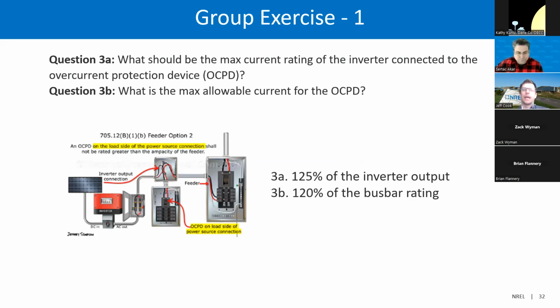And then for 3B, the maximum allowable current is 120% of the bus bar. So those are more of the common things you might see as issues, and you would typically see where they might have approved something on the plan, but you're seeing something installed larger or smaller out in the field than what's on the plan. And so that'd be something, of course, you'd reject. This is something that should be caught at plan review, and you're just verifying out in the field that what's installed matches what's on the plan. So I think we can move on from here.